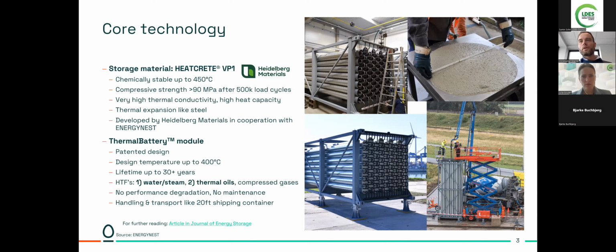And when we look at the pictures, we see what we call the thermal battery module. This consists of essentially two parts, steel and heatcrete. It's a steel frame designed as a 20-foot shipping container. And inside this frame, we have cylindrical thermal elements that consist of the heatcrete and cast-in steel pipe heat exchangers. In a way, it's like a shell and tube heat exchanger where you have the heatcrete on the shell side. So it's a very simple, very robust, long duration storage. There's no maintenance required on the module itself, and it's all welded steel piping.